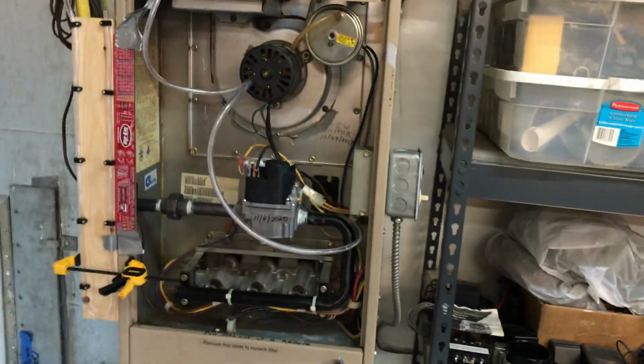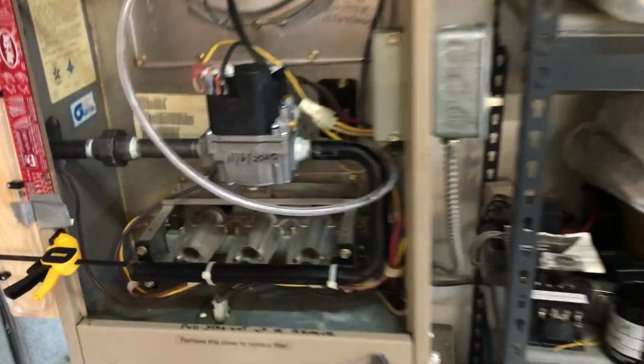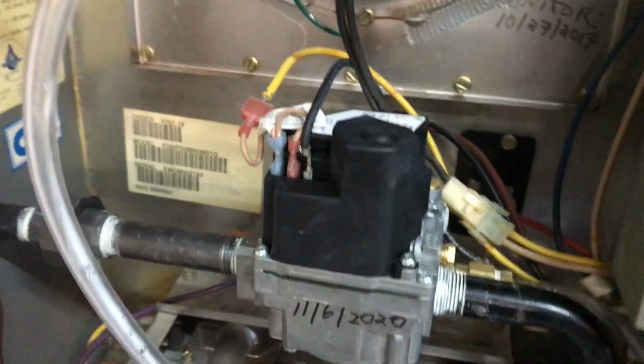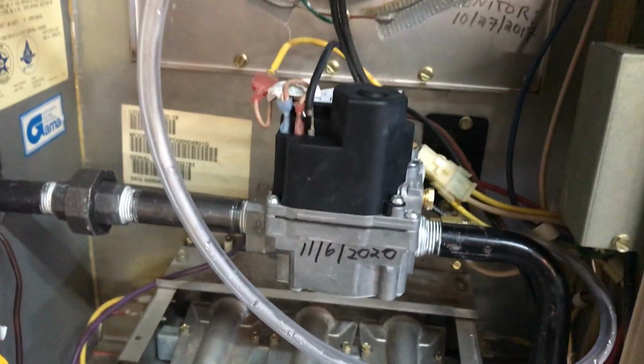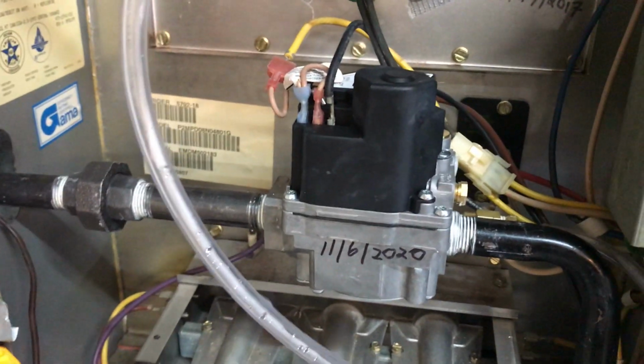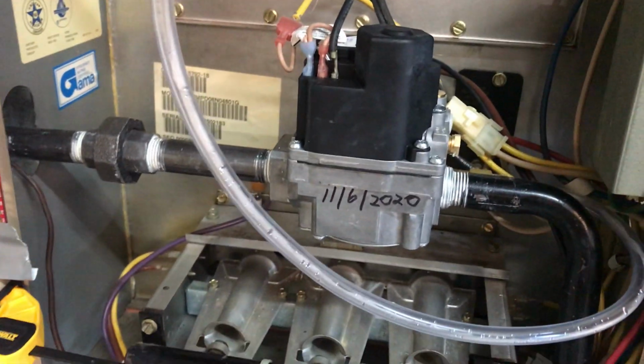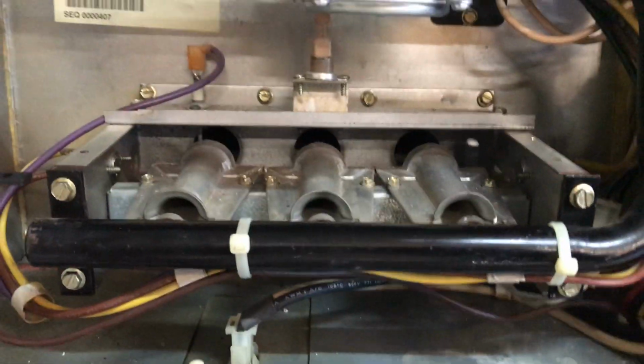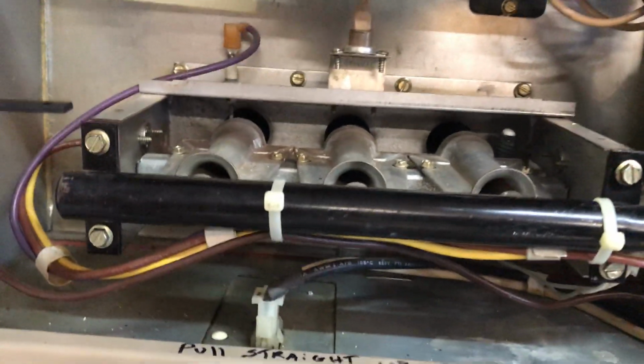In the furnace, I'm going to measure the water column pressure coming out of a new gas valve. My gas valve failed, and I put a new one in last night, maybe the night before. My buddy John helped me put it in, and it worked well. But then later last night, it kept kicking out after every 5 minutes or so of on, and it was giving 5 blinking error codes in a computer window.